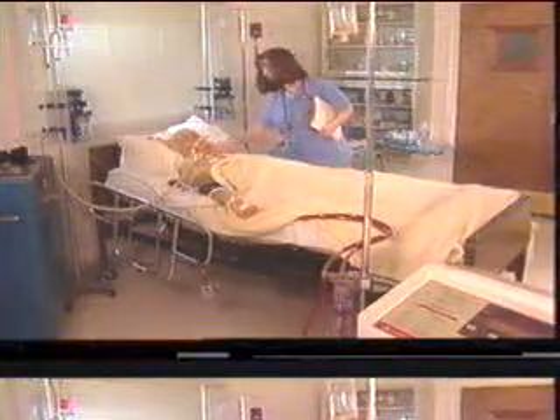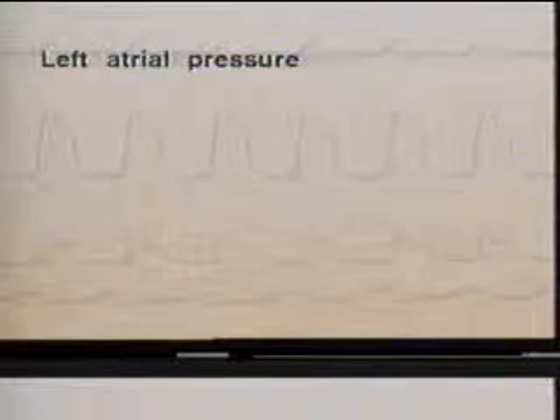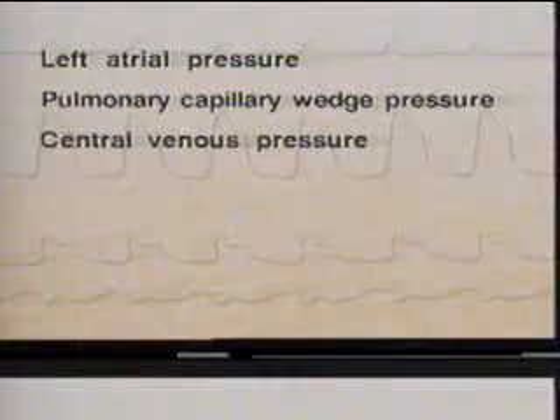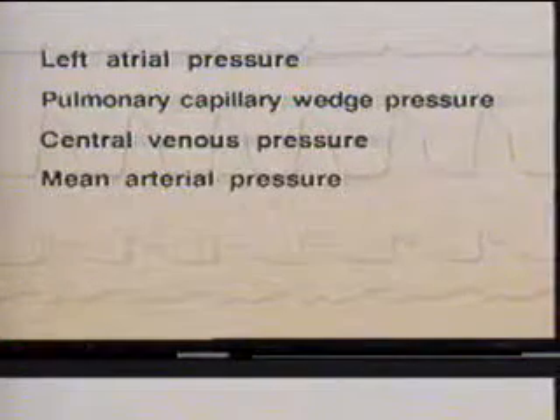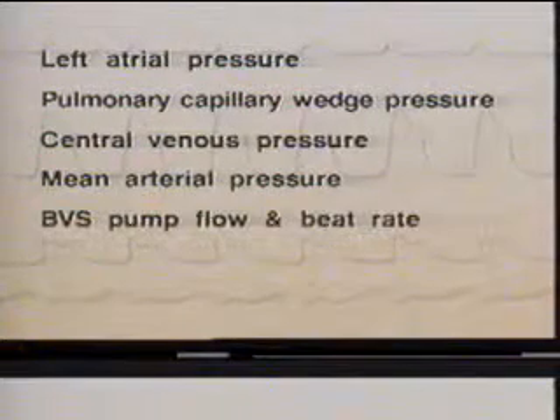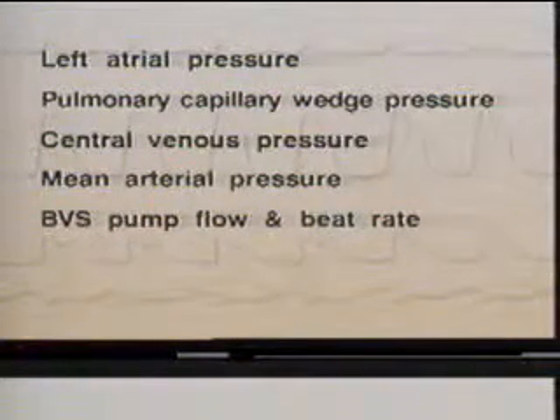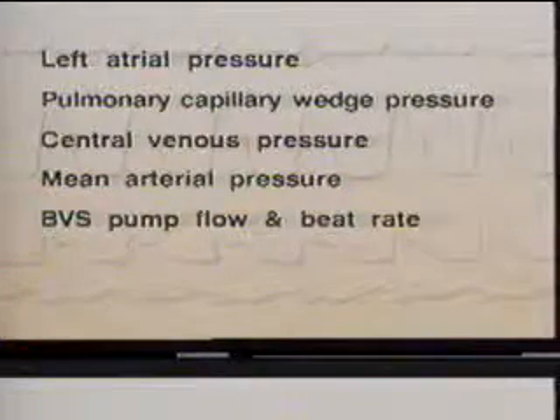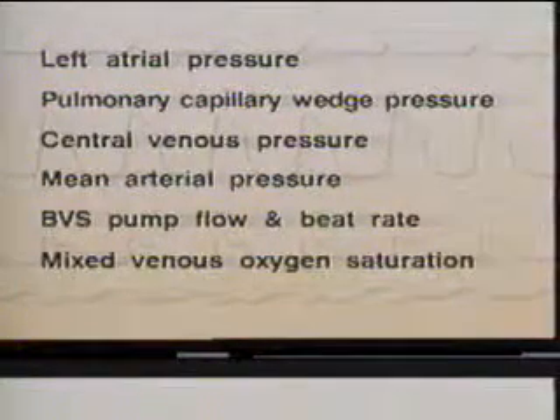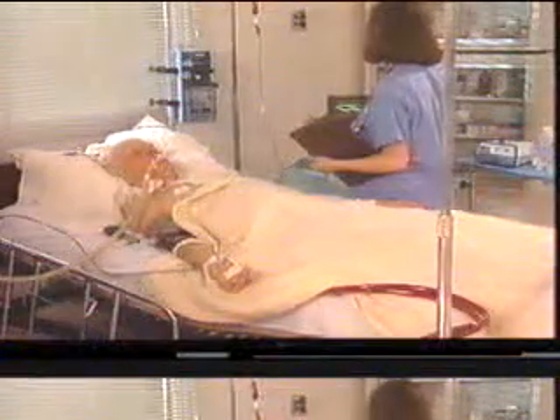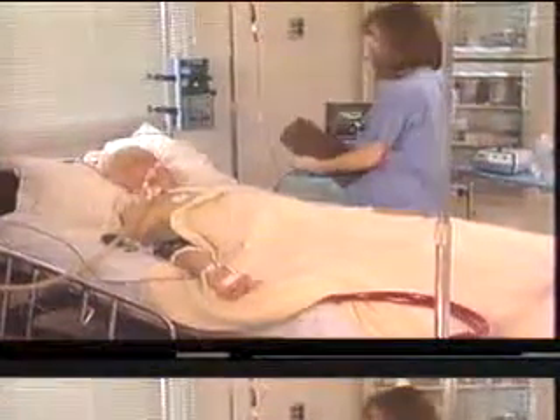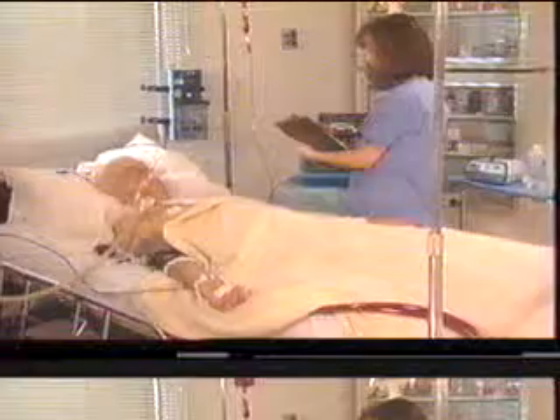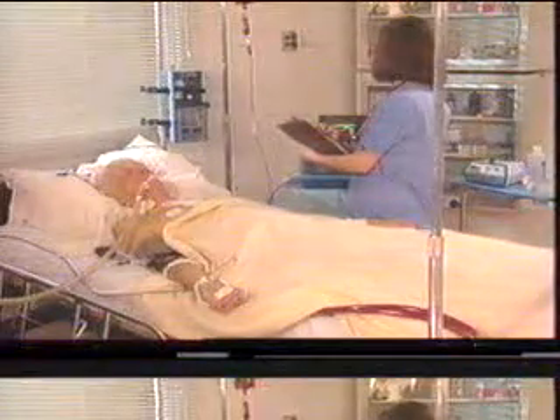Upon arrival in the unit and throughout the support period, hemodynamics should be carefully monitored. Filling pressures must be carefully assessed via measurement of left atrial pressure or pulmonary capillary wedge pressure, and central venous pressure. Mean arterial pressure should be continuously monitored, as well as pump flow and beat rate, as displayed on the BVS 5000 console. Continuous monitoring of mixed venous oxygen saturation is also recommended. Record hemodynamic parameters as dictated by hospital protocol. Note that whenever the right heart is supported, thermodilution cardiac output measurements from a pulmonary artery catheter will not be accurate.